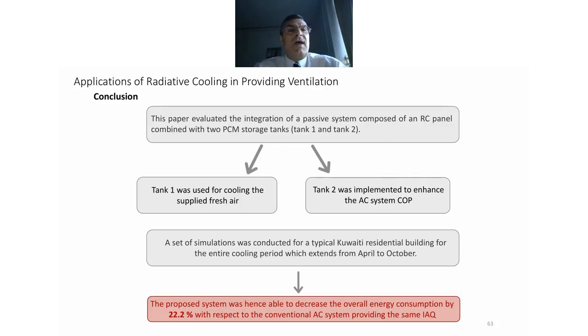In conclusion, this paper was submitted to the ASHRAE journal and is under review right now. We are using an RC panel coupled with two different tanks, varying the application between early night and late night. Tank 1 was used for ventilation, and Tank 2 was used to improve the COP of the air conditioning system. Running them together, we got a saving of 22% on average when coupling both applications together, which is a great percentage for this type of application. This is passive cooling.